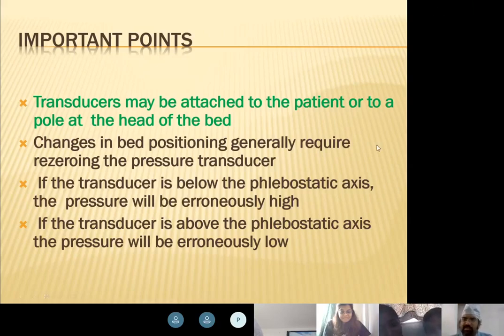So this used to happen because of the transducer. It's important for you to understand that a transducer below the phlebostatic axis will cause the pressures to go erroneously high, and if the transducer is above the phlebostatic axis, the pressures will be low.